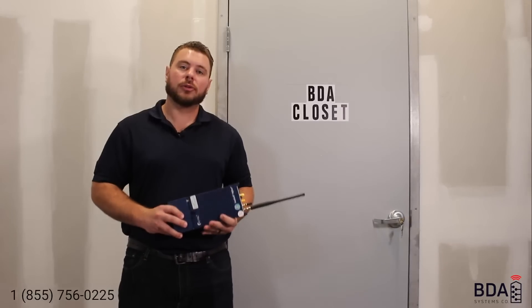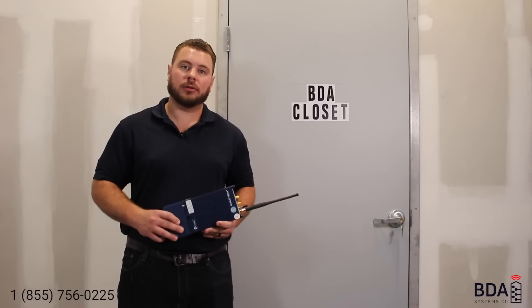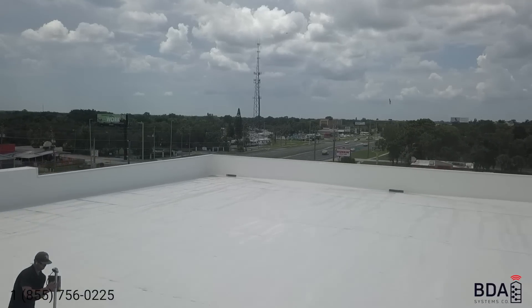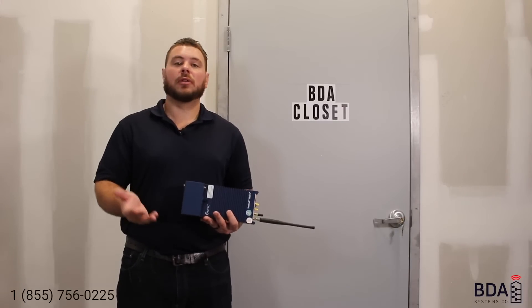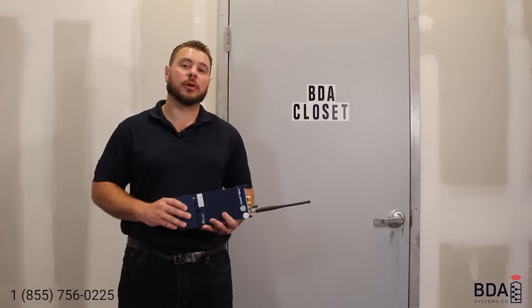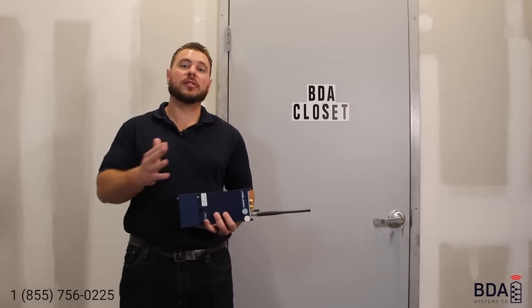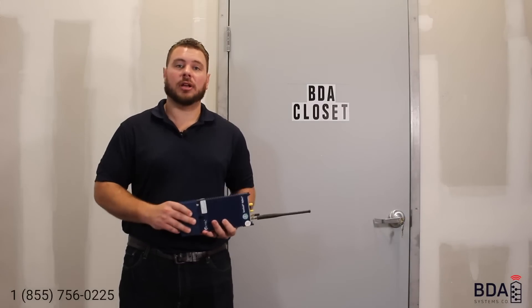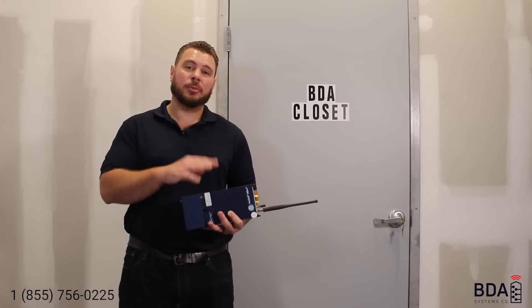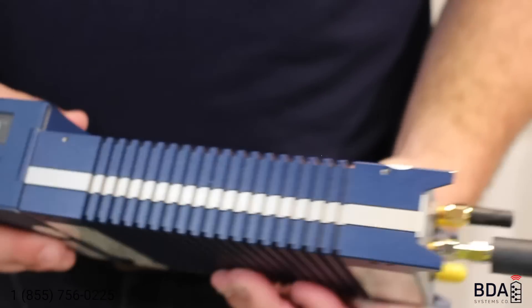Now let's talk about the tools of the trade. In order to do an RF signal survey, you need something called a spectrum analyzer. This device will be programmed to search for all the radio frequencies pertaining to that AHJ or carrier — AT&T, Verizon, T-Mobile, and Sprint. For a proper RF survey for an AHJ covering police and fire frequencies, your device has to be calibrated and approved by that AHJ. The one I have in my hand is a PCTEL SeeGull, which is approved by most AHJs and is calibrated often.